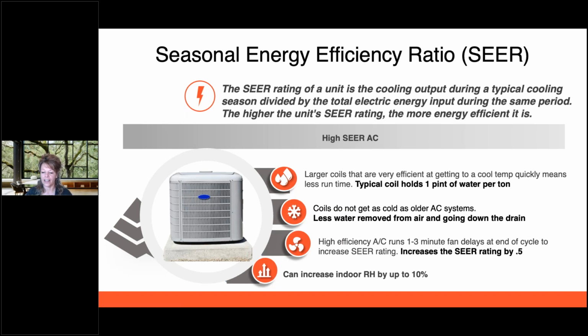And one way that they kind of cheat the system a little to increase the SEER rating is they will run the fan for 1 to 3 minutes after the compressor shuts off. So they're getting points for evaporative cooling, which, if you're in Arizona, probably isn't a problem. But if you're in a mixed humid climate, the AC runtime that you just used to remove water will be mitigated, because now you're going to increase the RH up to 10% by running that fan after the compressor shuts off, because it's all going to re-evaporate back into the house.